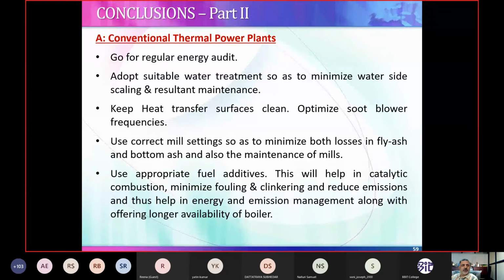Second part, very important, is to adopt suitable water treatment so as to minimize water side scaling and resultant maintenance. Once scaling is reduced from the same heat transfer area, you will improve your steam generation and enhance your efficiency.